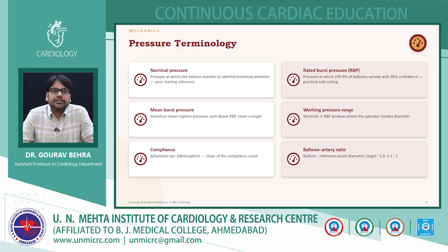Now, what is mean burst pressure? Mean rupture pressure is well above the RBP. So the RBP and mean burst pressure need not be achieved. You just work at nominal and always below the RBP.